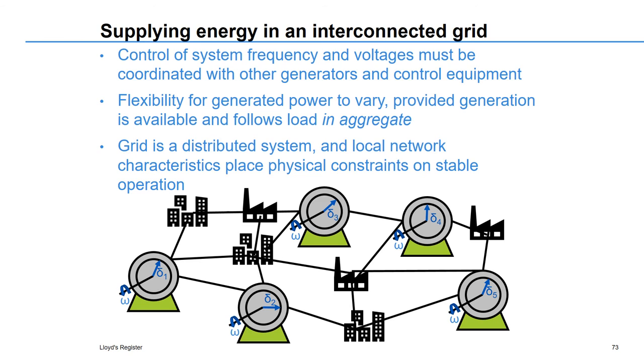Meanwhile, of course, it's no longer necessary for a single generator to exactly balance its local load. Nonetheless, the overall control of the system, as we know, needs to ensure that the total load is followed in aggregate by the total generation. So system strength issues arise here because of different locations for the generators and different levels of sensitivity, due to the characteristics of the network, of local voltages, of phase angles, and so on, to changes in power flow that occur from second to second in this network.